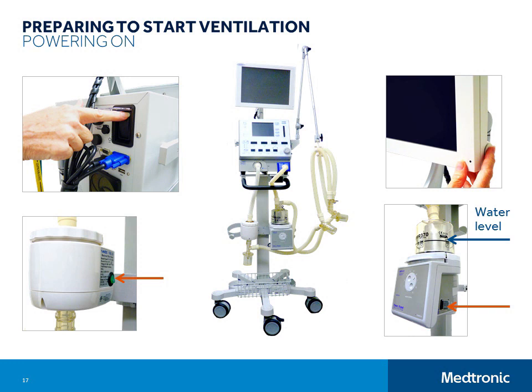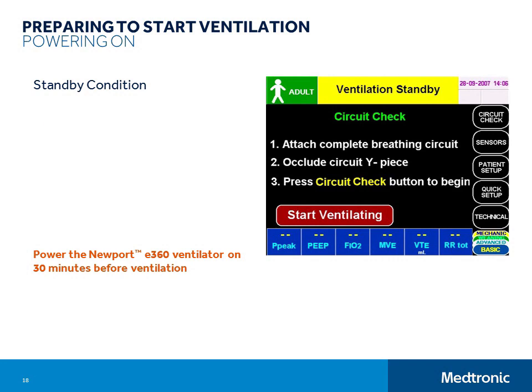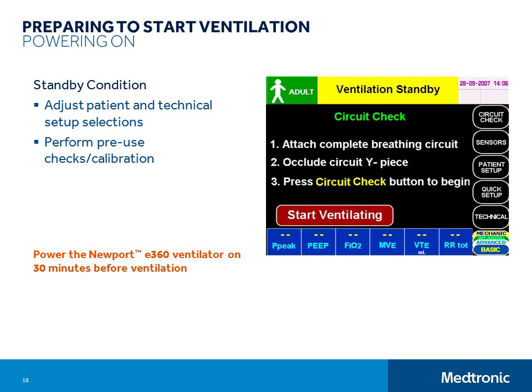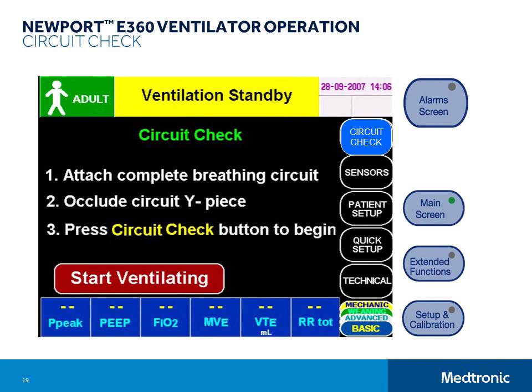While in standby condition, you can adjust patient and technical setup selections, perform the pre-use circuit check and calibrations, use quick setup to automatically adjust the ventilation and alarm settings based on ideal body weight, or manually adjust these settings. And of course, you can start ventilating. For the best ventilator performance, you should perform the circuit check and the oxygen sensor calibration each time you set up the ventilator for patient use. They are both quick and easy to do. The circuit check requires that the E360 be connected to a compressed air gas source, and the oxygen sensor calibration requires that the E360 be connected to a medical-grade oxygen source.